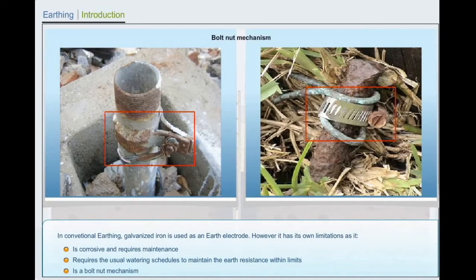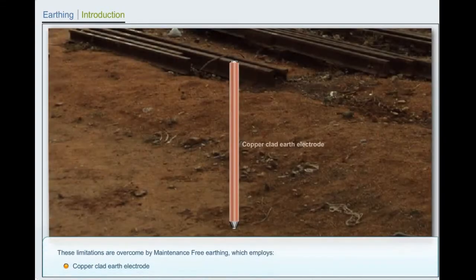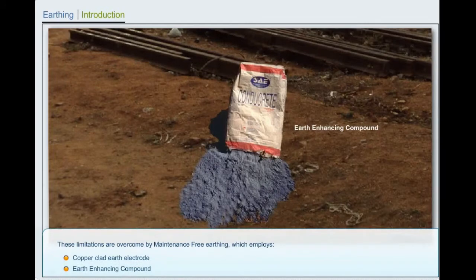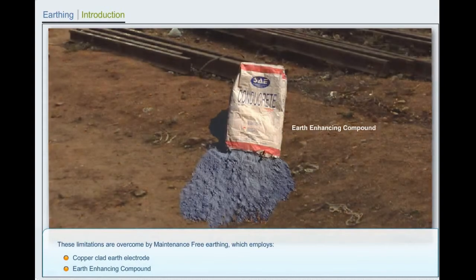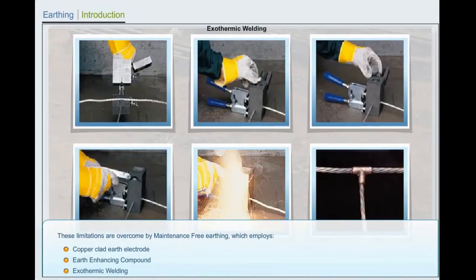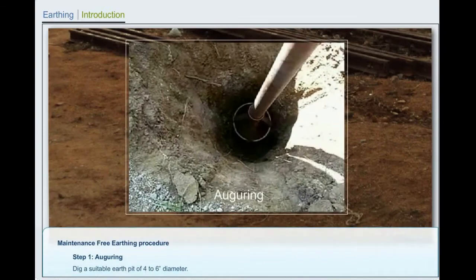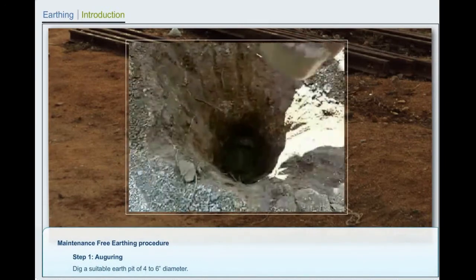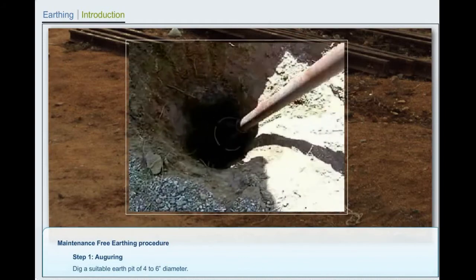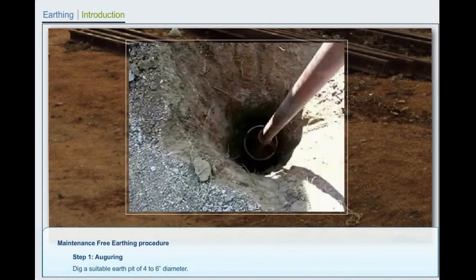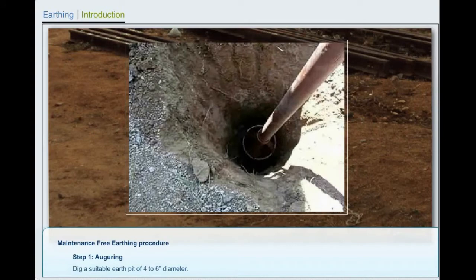Is a bolt nut mechanism. These limitations are overcome by maintenance-free earthing, which employs steel conductors called copper-clad pipes, graphitic compounds and non-corrosive salts called ground-enhancing material to avoid corrosion, and exothermic welding. Thus, maintenance-free earthing is required for installations where earths are not freely accessible for maintenance and measurements. Let us now discuss the maintenance-free earthing procedure in detail.